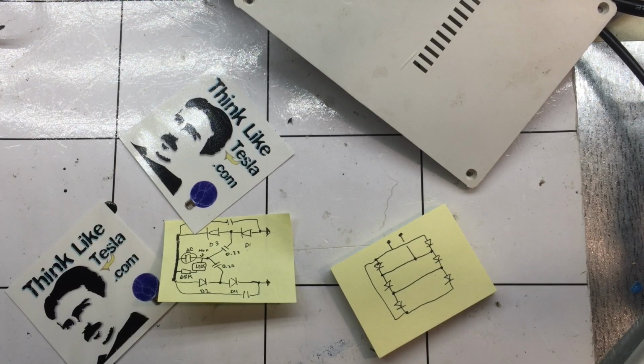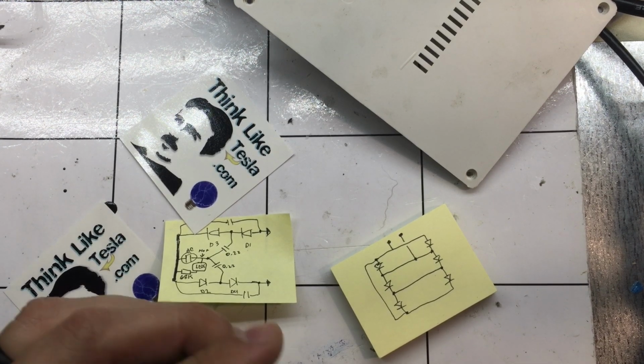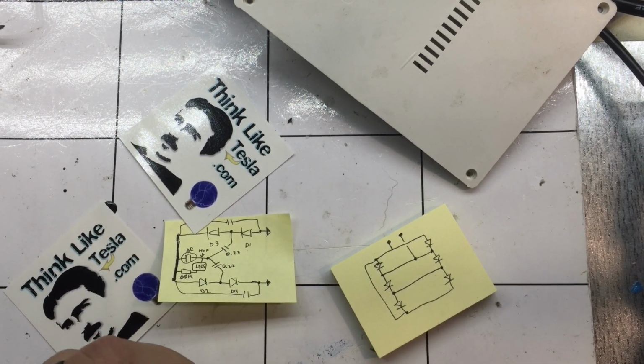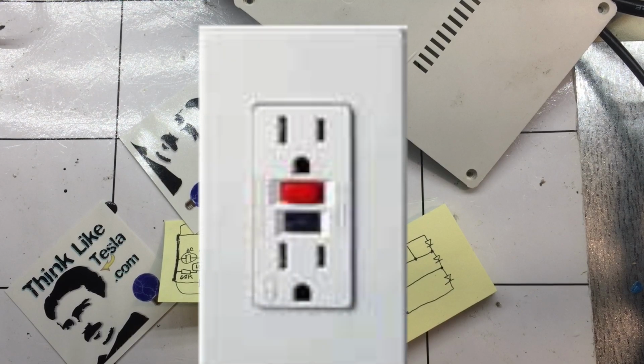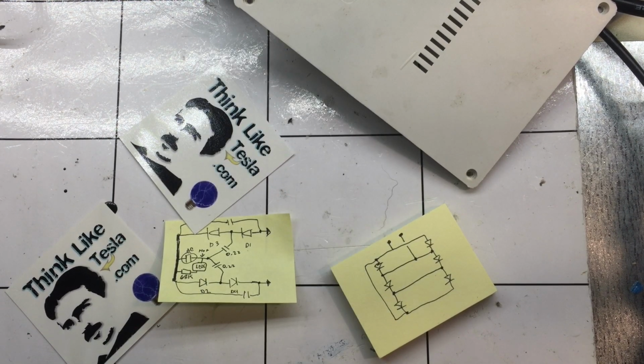Circuit breakers are there not to save you - they're to prevent the wiring from burning or melting, and the device from catching fire. Ground fault protection circuits are the things that protect you, the human being, because they trip off with very small amounts of current.